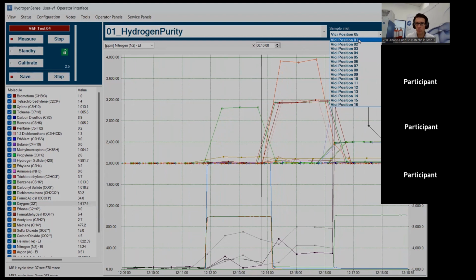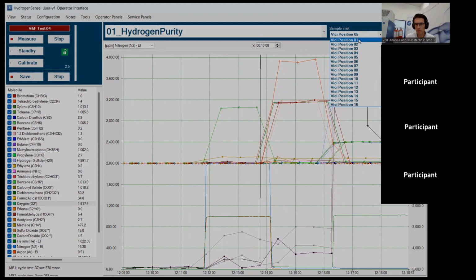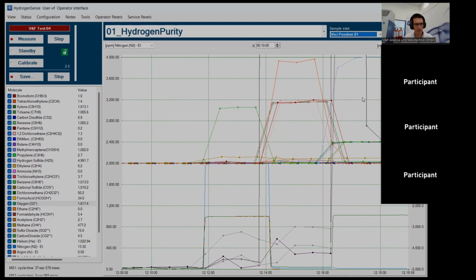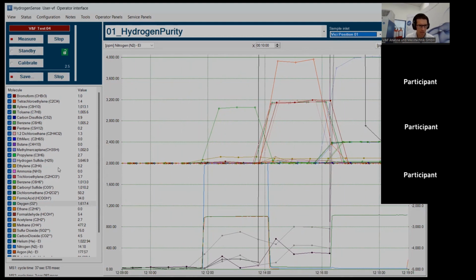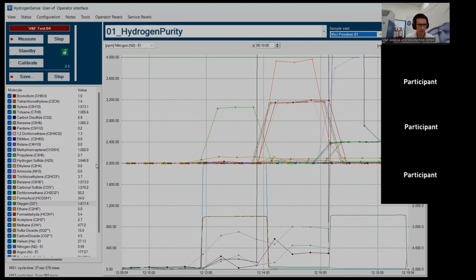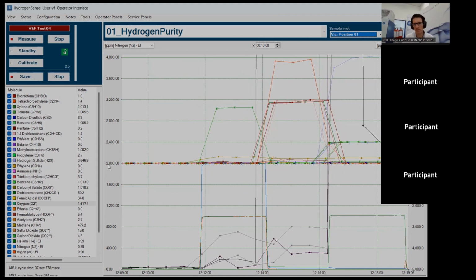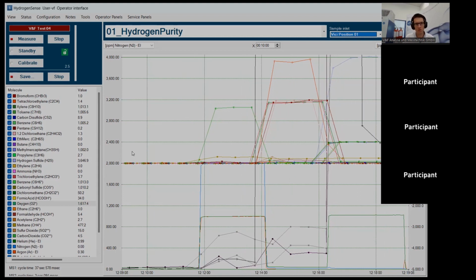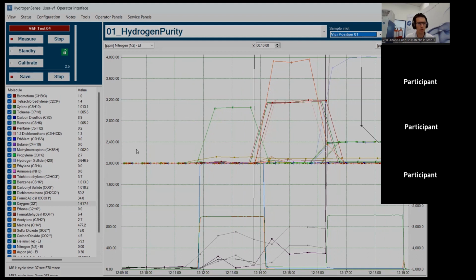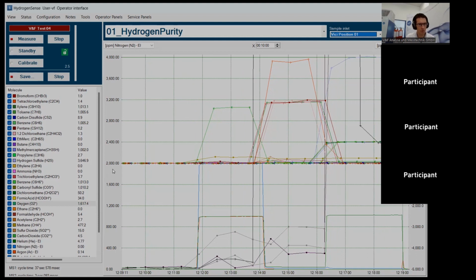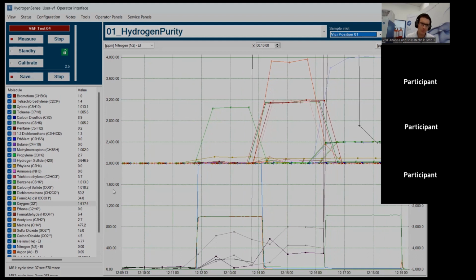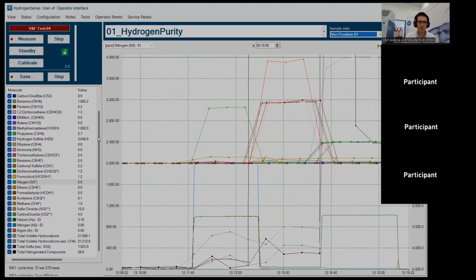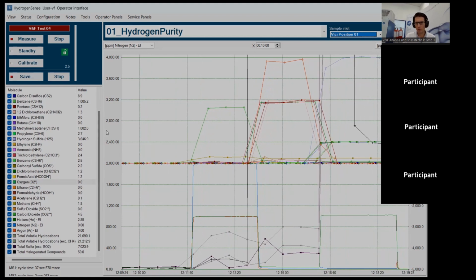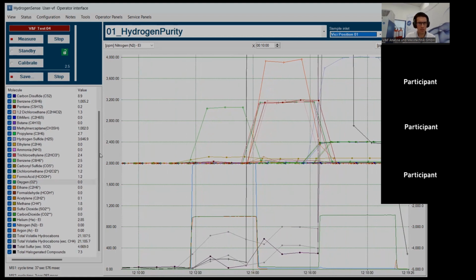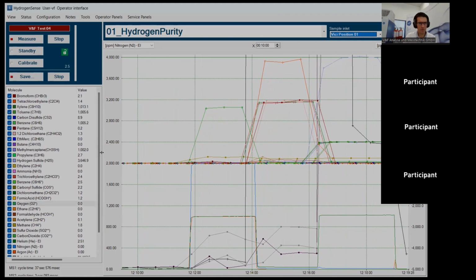So I'm going to switch over now to position 1, which is a 6.0 hydrogen calibration gas bottle. So this is our zero reference, you could say. This is also the gas that we would use in order to perform the zero calibration. So pretty much going to give it just a few cycles for all the signals to go down.